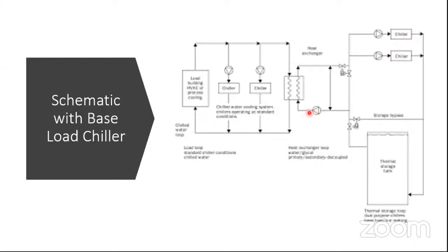This is our pump that is taking the water into the PHE. So this is our brine side. This is our water side. The only purpose to have the PHE is for it to act like a third chiller in here. So this is our base load. This is what the difference is in the schematic with and without base load.